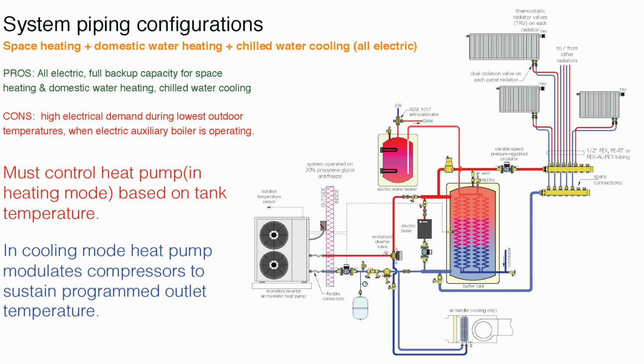Here's where we're adding an air handler for chilled water cooling. So now you see there's a diverter valve, and it simply steers the output from the heat pump. In heating mode, it goes up to the buffer tank. In cooling mode, it goes to the air handler. We've got a tank here with internal coils. There's a tank over there with internal coils if you want to look at it. That can serve as domestic water preheat, or complete heat, depending on what temperature you maintain that tank at.